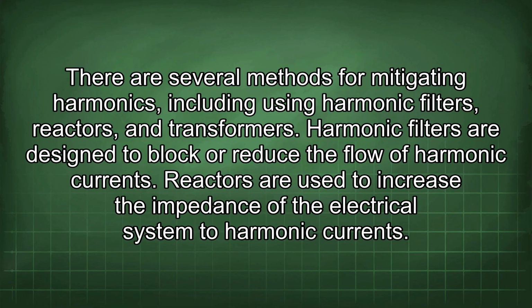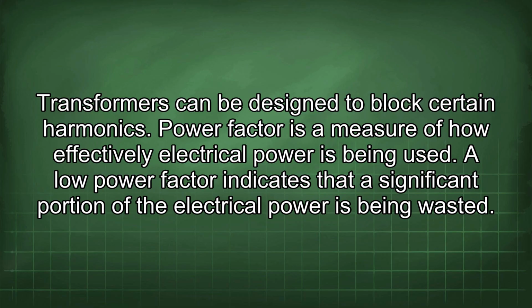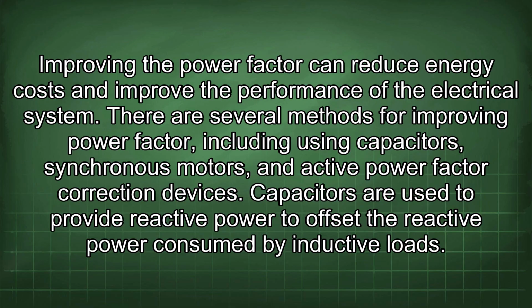There are several methods for mitigating harmonics, including using harmonic filters, reactors, and transformers. Harmonic filters are designed to block or reduce the flow of harmonic currents. Reactors are used to increase the impedance of the electrical system to harmonic currents. Transformers can be designed to block certain harmonics. Power factor is a measure of how effectively electrical power is being used. A low power factor indicates that a significant portion of the electrical power is being wasted. Improving the power factor can reduce energy costs and improve the performance of the electrical system.